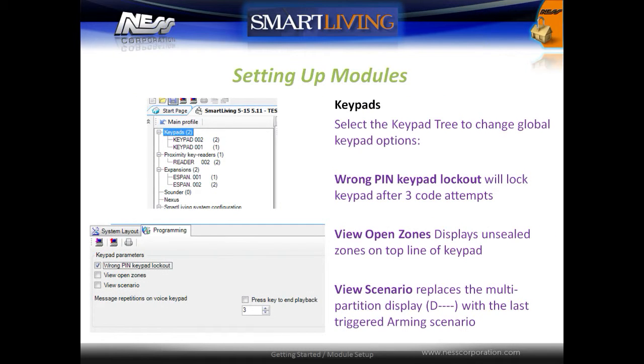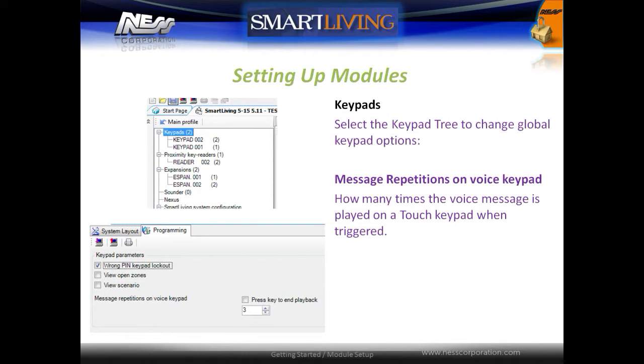Select the Keypads tree to change global options for the keypads. Wrong Pin Keypad Lockout will lock keypads after three failed attempts to enter a code. View Open Zones displays unsealed zones at the top of the keypad, and View Scenarios replaces the multi-partition arming status with a single arming scenario. The Message Repetitions option is for touchscreen keypads and adjusts how many times a voice message is played.